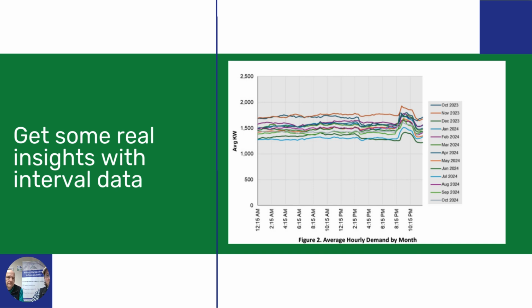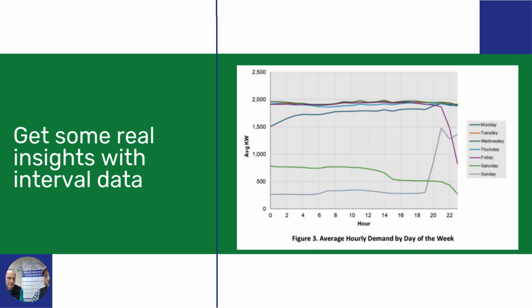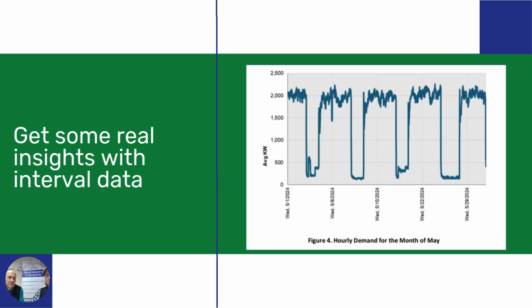And that's where we go here when we were talking about that previous slide a minute or two ago, where they're continuously using 250 kW every day, every hour. We got really deep in that for a month period of time and looked at, when is that happening?